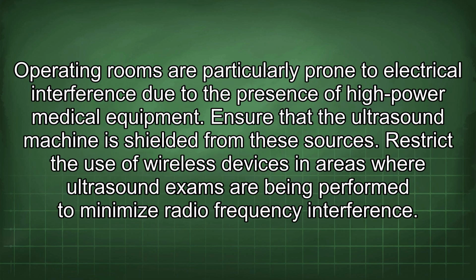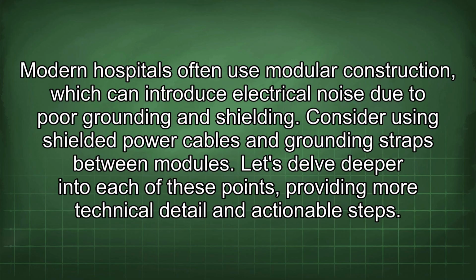Operating rooms are particularly prone to electrical interference due to the presence of high-power medical equipment. Ensure that the ultrasound machine is shielded from these sources. Restrict the use of wireless devices in areas where ultrasound exams are being performed to minimize radio frequency interference. Modern hospitals often use modular construction, which can introduce electrical noise due to poor grounding and shielding. Consider using shielded power cables and grounding straps between modules. Let's delve deeper into each of these points, providing more technical detail and actionable steps.